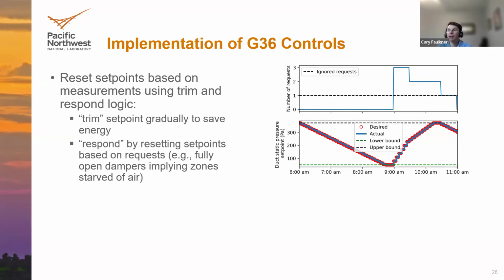An example of what might generate these requests for a VAV system is the damper position measurements. For example, you might trim your static pressure set point, which can potentially lead to less airflow. But if you have significantly opened dampers, that means the zones are starved for air. That's going to generate a request fed to this controller, saying there are 2 zones requesting more air, and then the controller will respond accordingly and increase the set point.